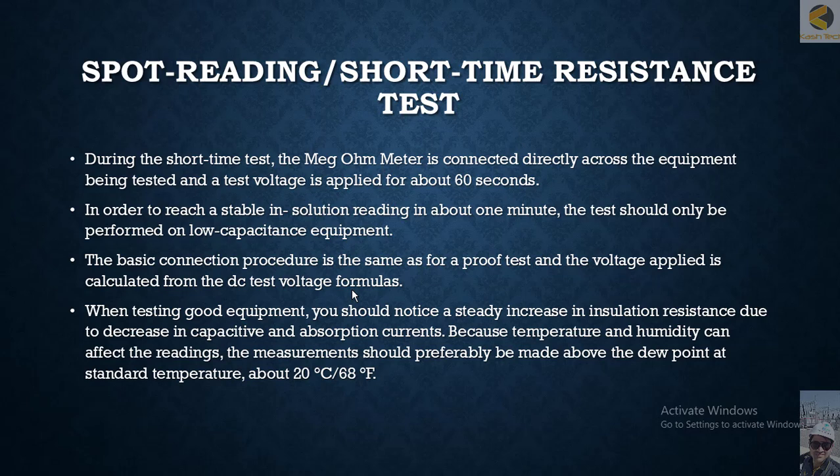During the short time test, the megaohm meter is connected directly across the equipment being tested and a test voltage is applied for about 60 seconds in order to reach a stable insulation reading. The test should only be performed on low capacitance equipment, as with large capacitance equipment the reading will not be stable within one minute. The basic connection procedure is the same as for the proof test, and the voltage applied is calculated from the DC test voltage formula.